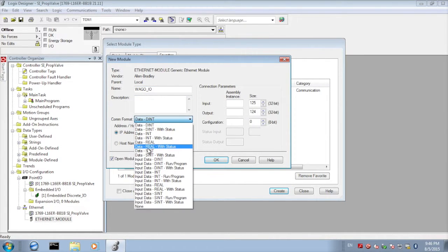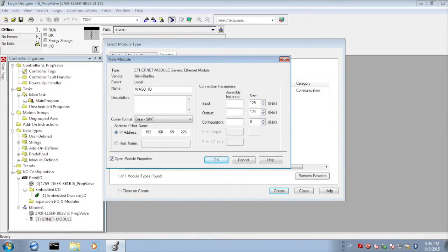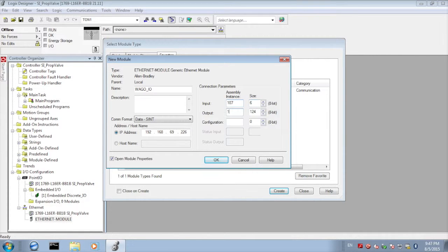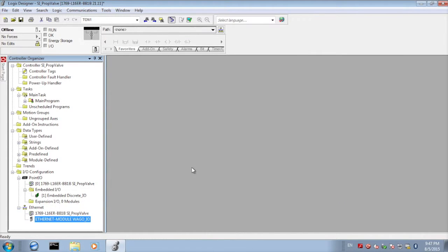We're going to change the data type to SINT. We'll add our IP address and under assembly instances we're going to use 107 and 101 each with six SINTs of data in configuration 1. We'll click create and click OK.